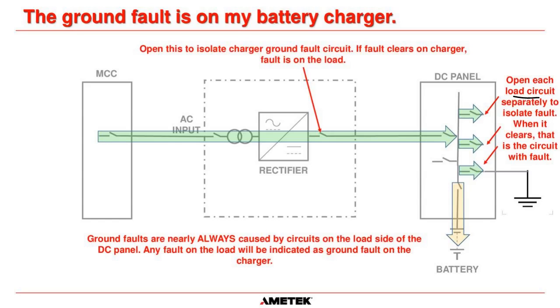Obviously, to do this, especially to open each load circuit, you have to take a load outage. There are devices that you can use. Megger does one. It's called a ground fault detect circuit. What you do is you connect a signal generator and send a signal between the pole of the battery or the charger that has the fault on it and ground, and then you put a transducer on each circuit, and basically you're hunting to see which circuit sees that signal that you're sending out along the ground path, and it can tell you without turning off the circuits which branch has the ground fault on it. They can be a little bit tricky to use, but I've used them quite a lot, and they're very good for finding ground faults without having to turn off the circuits.